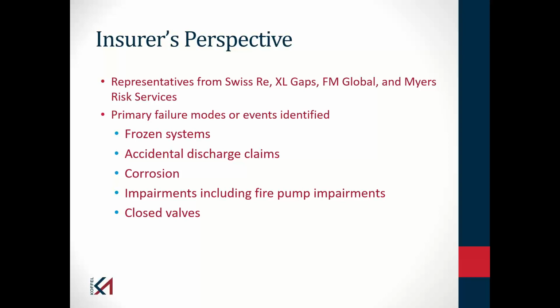And I said, but I have a question. When was this work done? And he said, 4 years ago. And I said, you understand that's not good news? They said, well, why not? I mean, he was looking to subrogate this and sue the roofing contractor. I said, because NFPA 25 requires a monthly inspection of the valve to verify that it's in a fully open position. This valve was electrically supervised, but it had been closed. I said, how do I explain that, one, we ignored any supervisory signal when the valve was first closed 4 years ago, and secondly, that we did 48 inspections and failed to identify that that valve was closed?